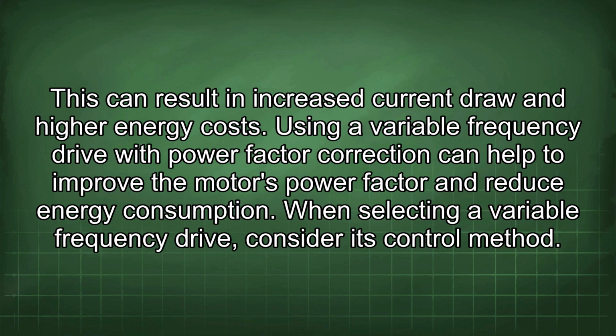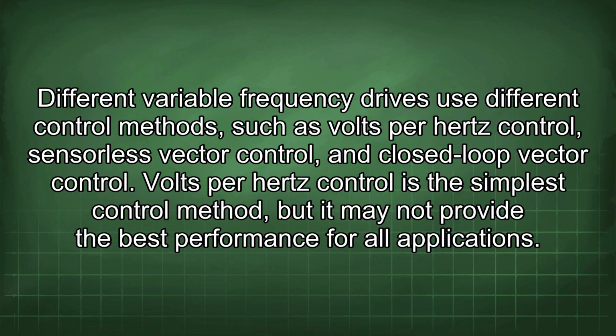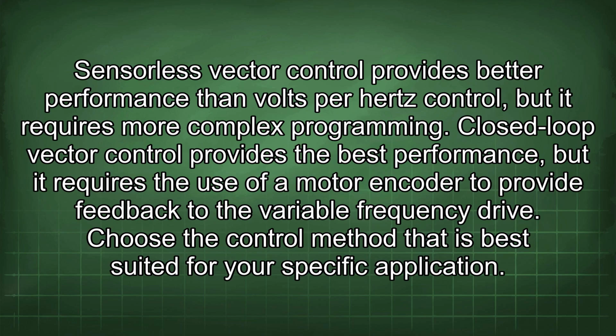Using a variable frequency drive with power factor correction can help to improve the motor's power factor and reduce energy consumption. When selecting a variable frequency drive, consider its control method. Different variable frequency drives use different control methods, such as volts per hertz control, sensorless vector control, and closed-loop vector control. Volts per hertz control is the simplest control method, but it may not provide the best performance for all applications. Sensorless vector control provides better performance than volts per hertz control, but it requires more complex programming. Closed-loop vector control provides the best performance, but it requires the use of a motor encoder to provide feedback to the variable frequency drive. Choose the control method that is best suited for your specific application.